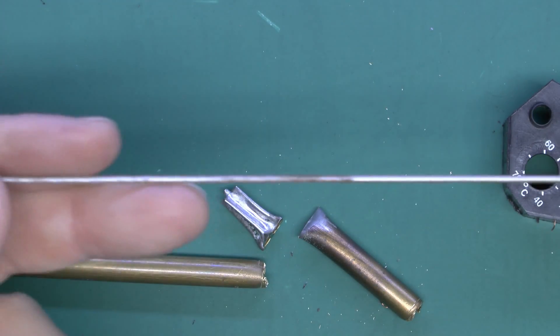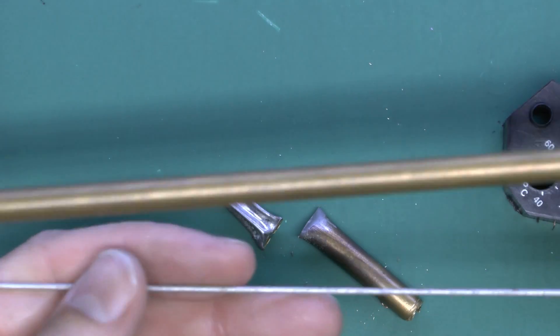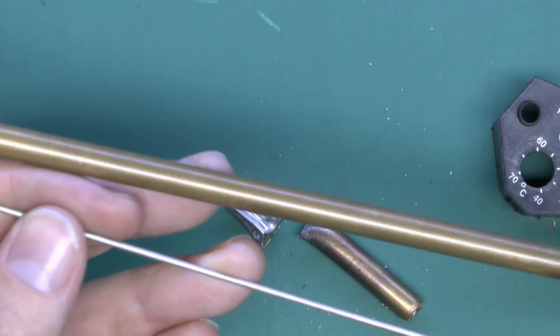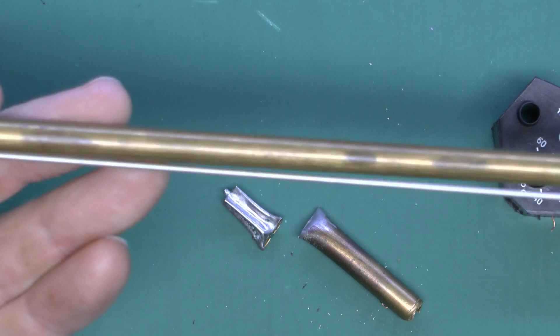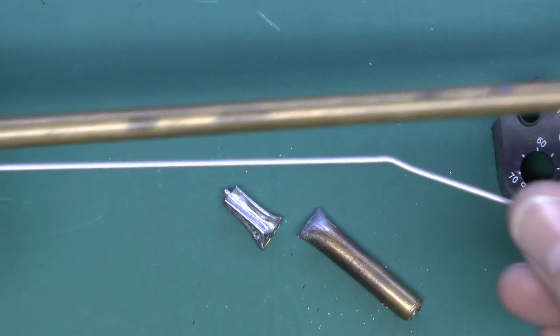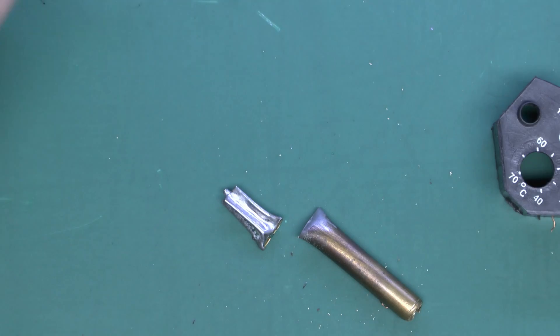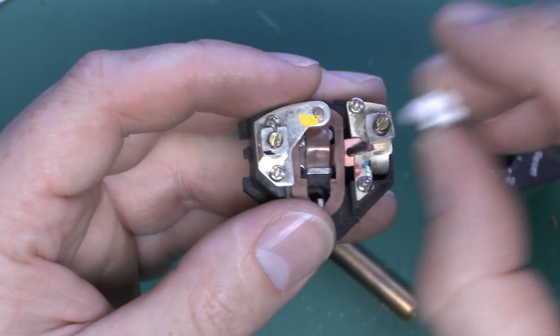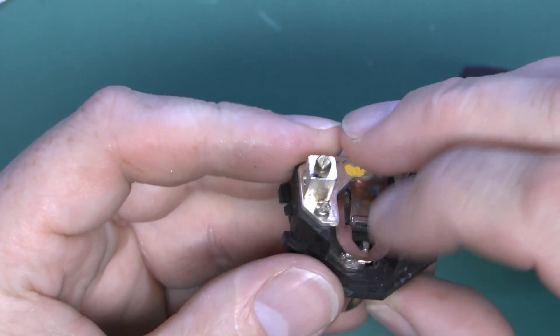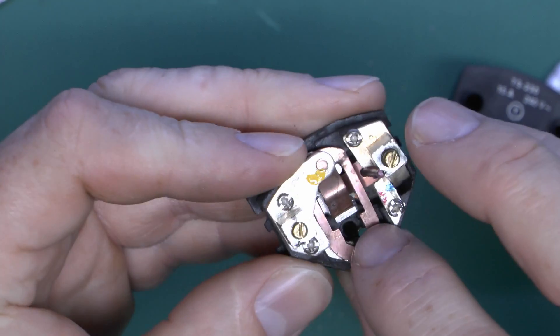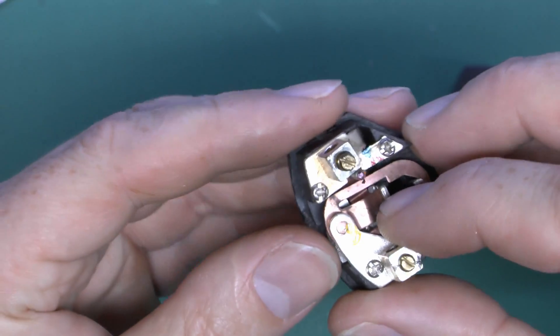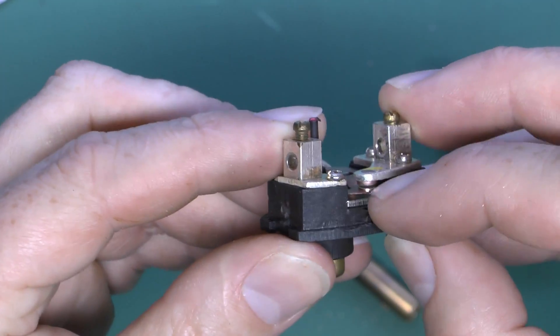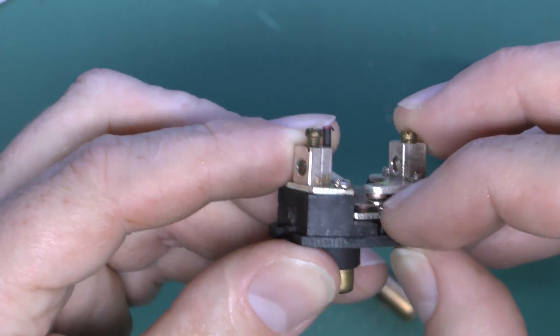So essentially, it's the whole length of the thing which is inside the tube. The rod, obviously expanding and contracting with reference to the outer, probably brass or something, tube there. Of course, that will just move slightly as the temperature varies a bit. And then that's what will press onto the little white piece here, going through and just adjust the two contacts either to the open or closed position there. So simply acting on that central piece and the way that it's formed. So there's like a spring in the middle so that it always springs into the one position there once the rod is removed.